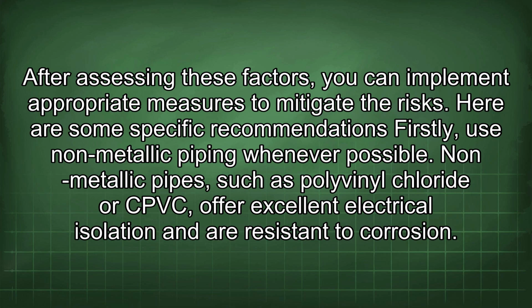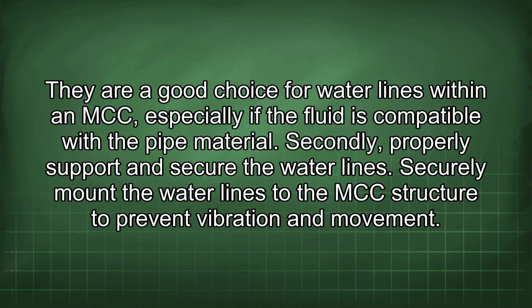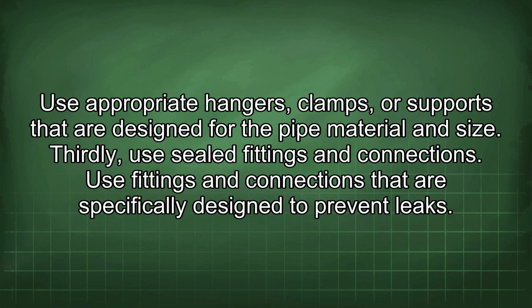Firstly, use non-metallic piping whenever possible. Non-metallic pipes, such as polyvinyl chloride or CPVC, offer excellent electrical isolation and are resistant to corrosion. They are a good choice for water lines within an MCC, especially if the fluid is compatible with the pipe material. Secondly, properly support and secure the water lines. Securely mount the water lines to the MCC structure to prevent vibration and movement. Use appropriate hangers, clamps, or supports that are designed for the pipe material and size.